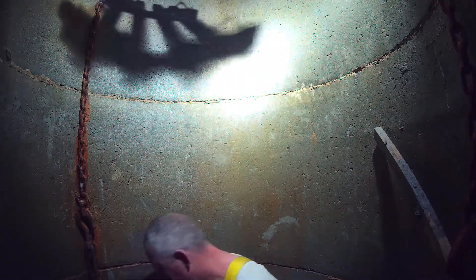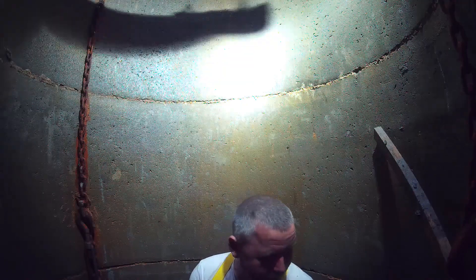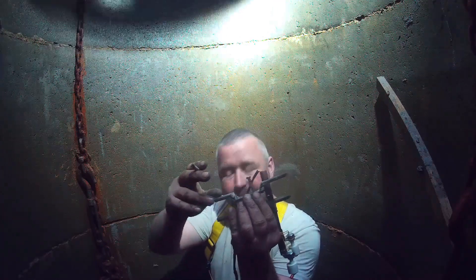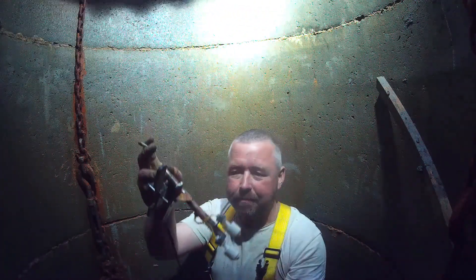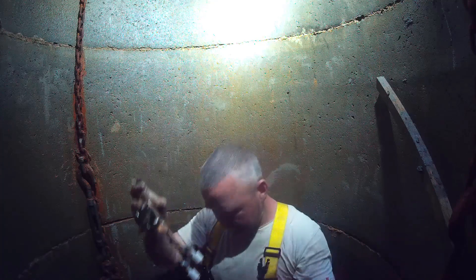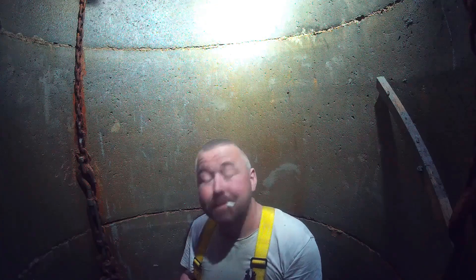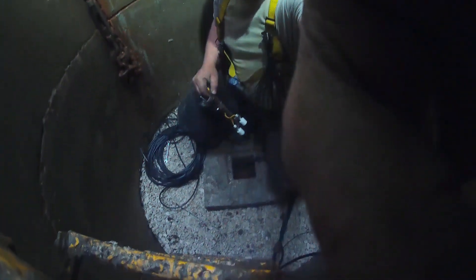Foam floats. I don't like this setup — I don't like this pump for the job. I've got a feeling we're going to end up doing some more experimenting with some of the pumps that failed due to sediment. This is the setup: it's going to clamp onto what will eventually be the grating ring of the sump, and we've got two floats very close together. They should be just about at the top of the pump. Let's see if we can fit this in a satisfactory manner — I've already tested it up top so I know it works. We've got to run the wire up in the caging on the side of this pipe.